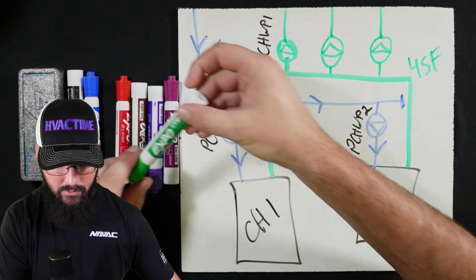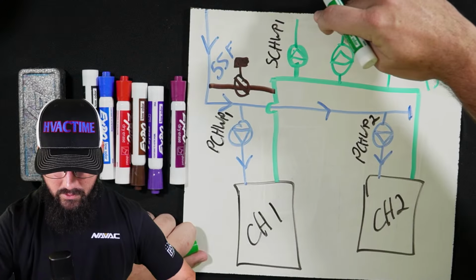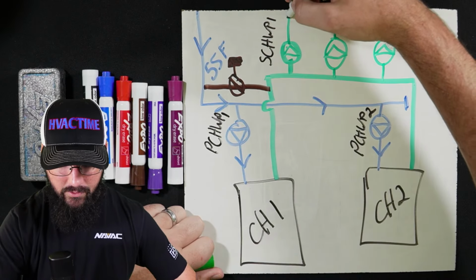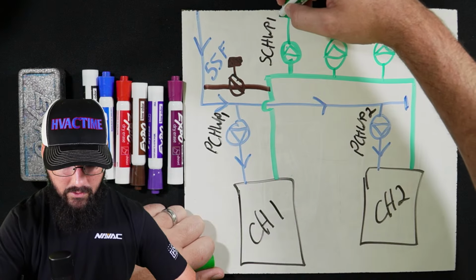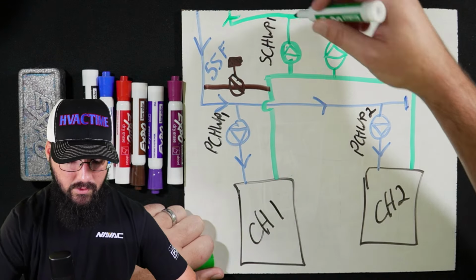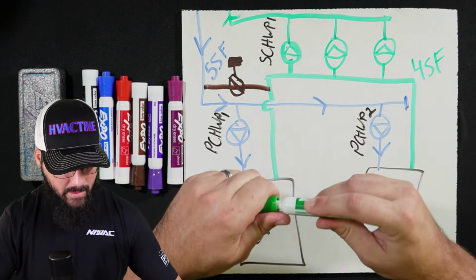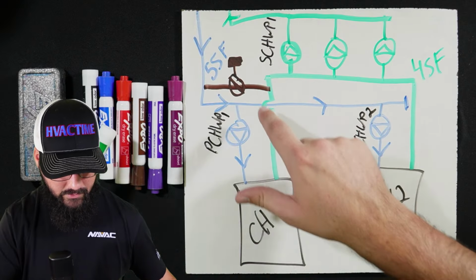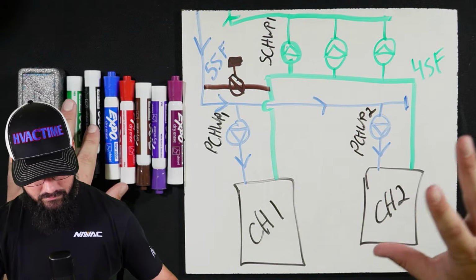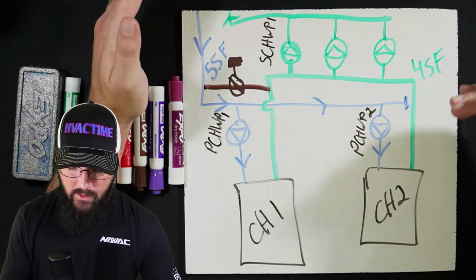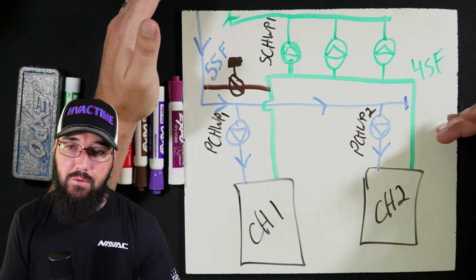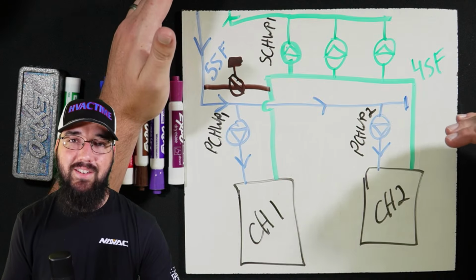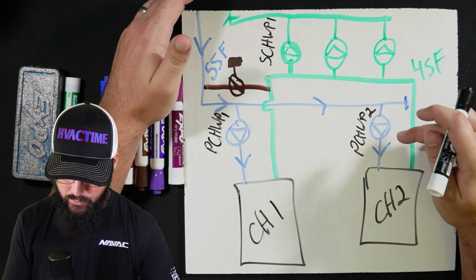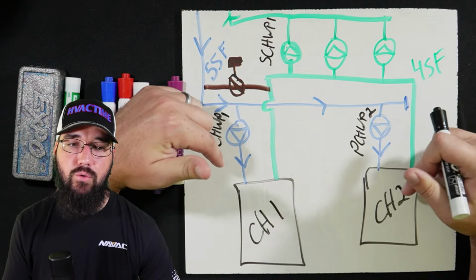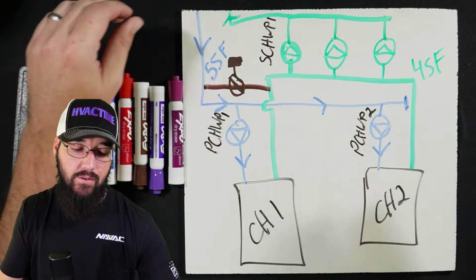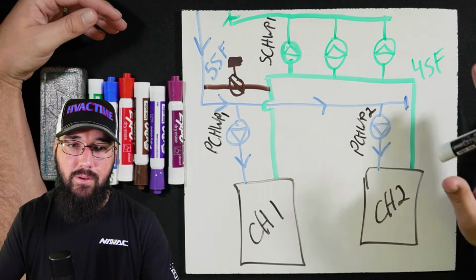These up here, by the way, I didn't draw this, I should have, feed into a header, and then this header flows out to the load. Technically, this should be between the headers. We're just going to go with it. So the staging process, that was the core premise of the question. How are we going to sequence this plant? These pumps are dedicated to the chillers. Each chiller has its own primary pump with a setup like this.